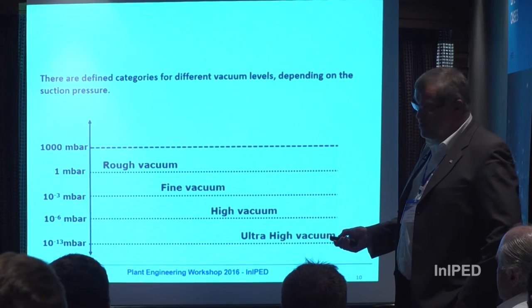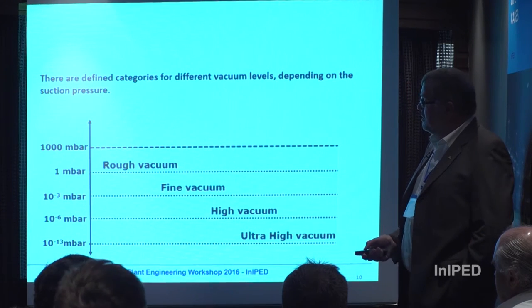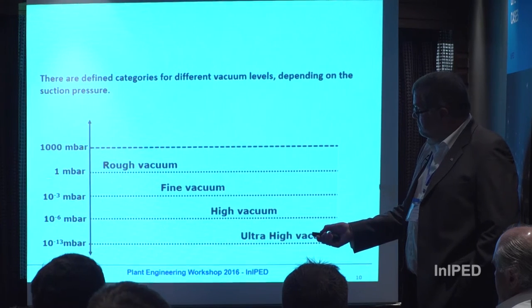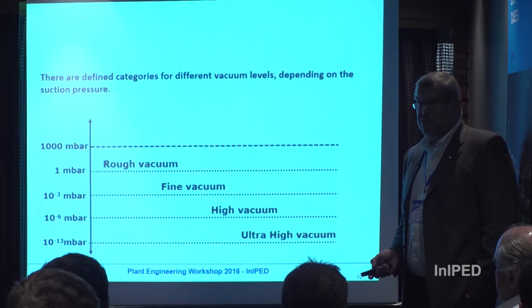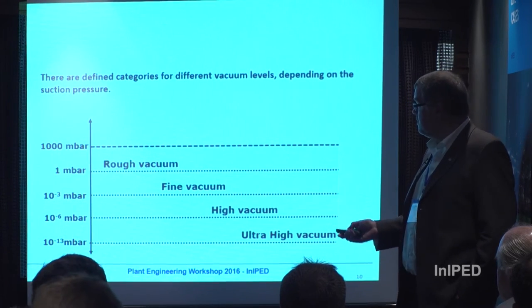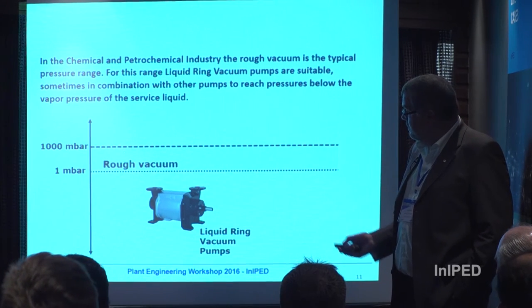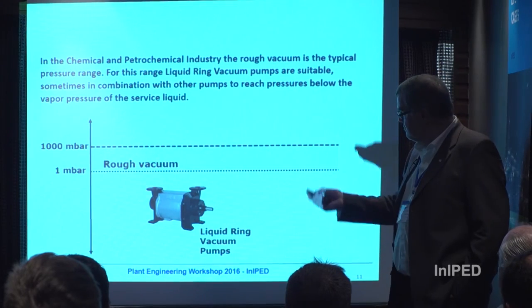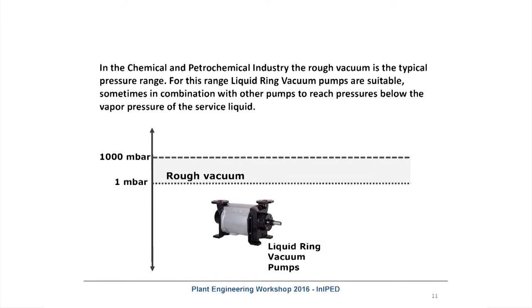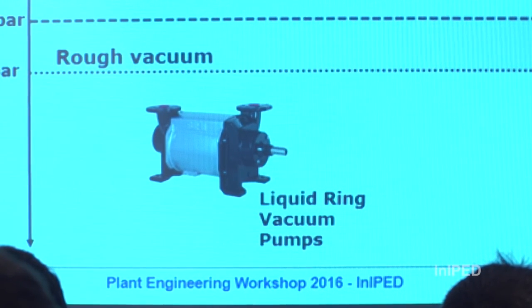On the vacuum side, we have different defined steps of vacuum. There is the rough vacuum, which starts at one millibar absolute up to ambient pressure. Fine vacuum goes down to ten minus three millibar, high vacuum to ten minus six, and ultra-high vacuum down to ten minus thirteen millibar. For applications in chemistry and petrochemistry, we are normally in the range between one millibar and atmospheric pressure — and this is the range where liquid ring machines operate. For lower pressures, liquid ring machines are not suitable, because you can only decrease pressure down to slightly above the evaporation pressure of the service liquid; otherwise the pump fills with steam and cannot operate anymore.